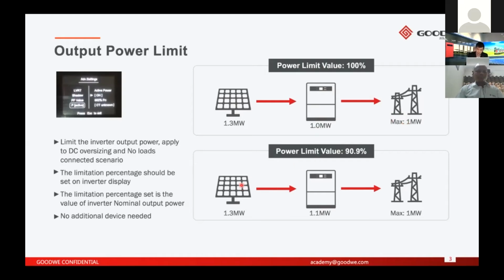But in this other case, you can see the inverter capacity is 1.1 megawatt, and the maximum output to the grid is 1 megawatt. So you need to set the power limit value in the display to 90.9%. Okay, so that's the output power limit.